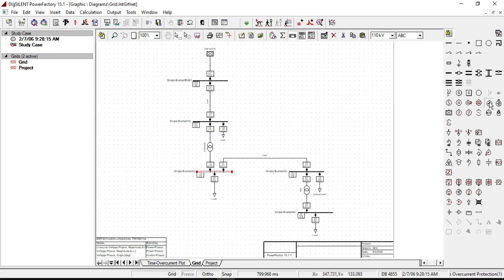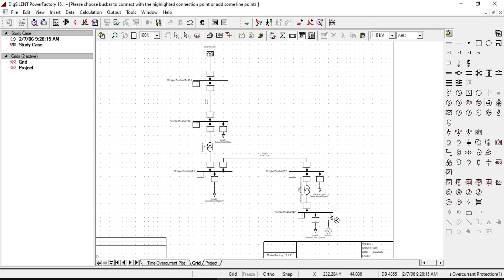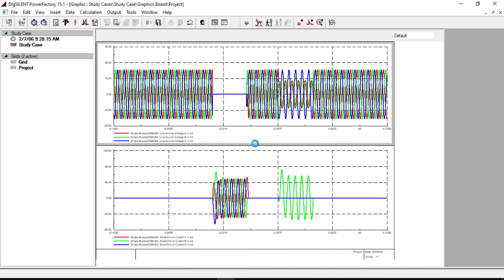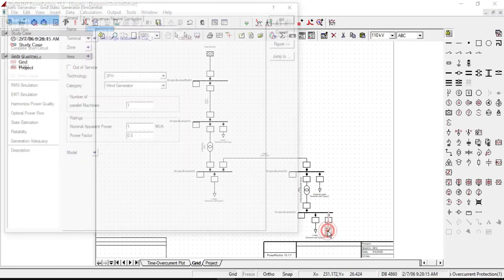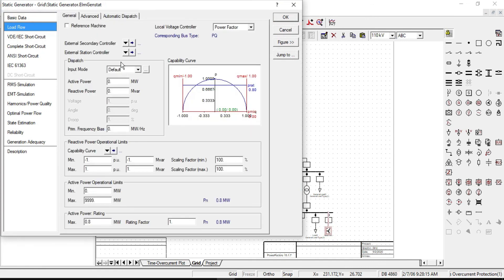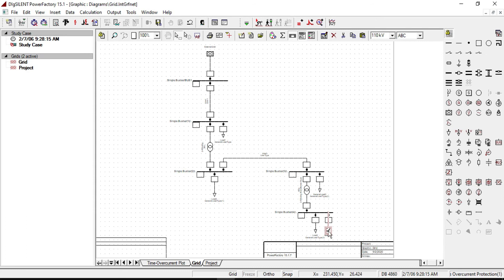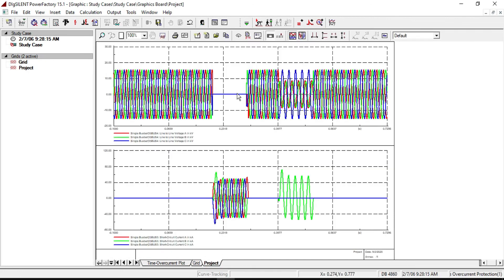Let's add a wind farm to this bus. Select P, cos phi for input mode, 1.5 megawatt for active power, and 0.9 for power factor. Now we have a wind farm in the network system. In case of fault, power can be supplied from the wind farm and the whole system will not turn off. So all bus bars will not be fully interrupted, and when fault occurs on bus 3, it may have less effect on bus 4. Let's check the waveforms.